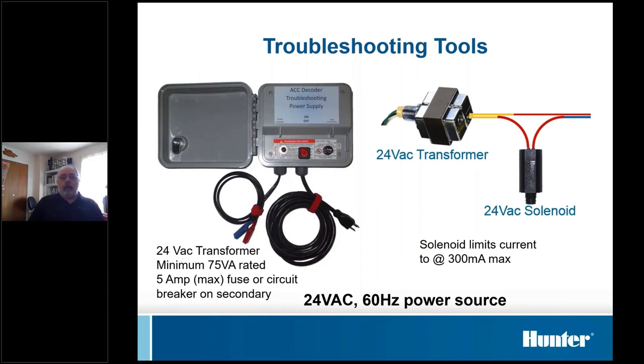You can use any transformer, even smaller transformers, as long as you put a solenoid in line with one of the wires. The solenoid limits current down to about 300 milliamps, a little bit more than what a solenoid draws. Basically, you can think of it like putting a piece of 1-inch pipe in the middle of a 6-inch main, where we're restricting the amount of current that can go down the wire by putting that solenoid in there. It makes it safer and gives us the ability to use a smaller transformer. Most guys don't have a big 3-amp transformer sitting in their truck, but most of them have one for a Pro C in their truck. And you can use it as long as you put that solenoid in line with it.